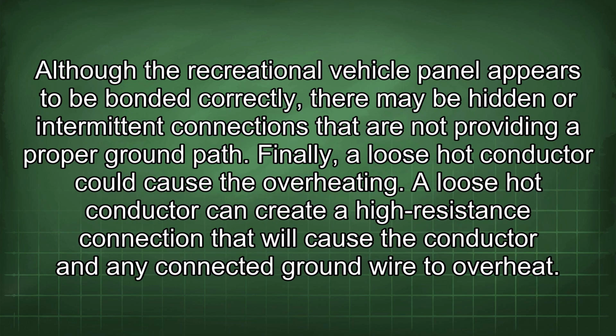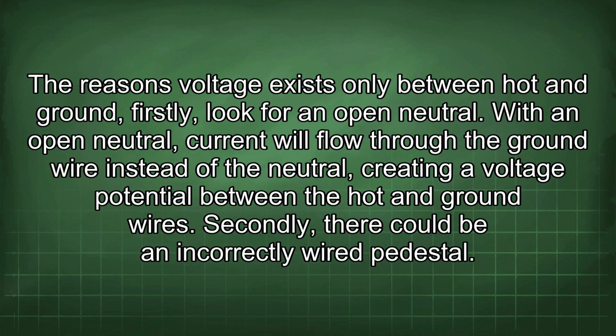Although the recreational vehicle panel appears to be bonded correctly, there may be hidden or intermittent connections that are not providing a proper ground path. Finally, a loose hot conductor could cause the overheating. A loose hot conductor can create a high resistance connection that will cause the conductor and any connected ground wire to overheat.